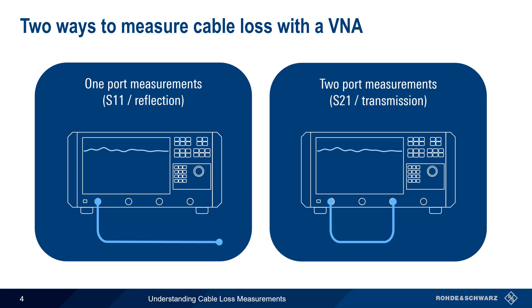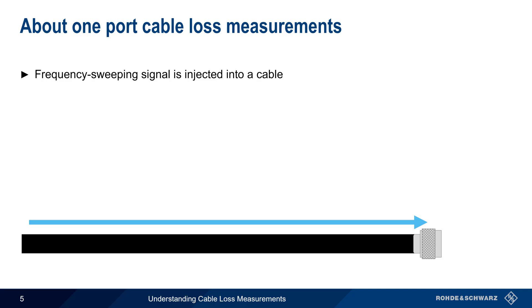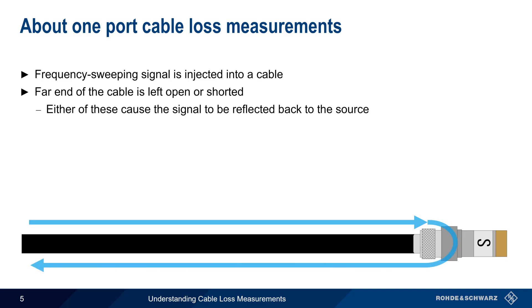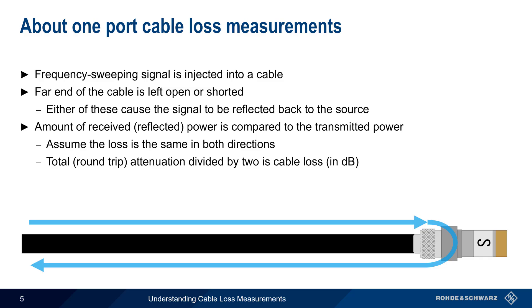We'll cover both of these methods in this presentation, starting with one-port measurements. In one-port measurements, a source or tracking generator is used to inject a signal into a cable. The frequency of the signal is swept over a user-defined range. The far end of the cable is either left open or is terminated with a short. Either of these conditions will cause the signal reaching the end of the cable to be reflected back to the source. At the source port, the amount of reflected power is compared to the known transmitted power. Assuming the loss is the same in both directions, the total or round-trip attenuation divided by 2 is the cable loss in dB.